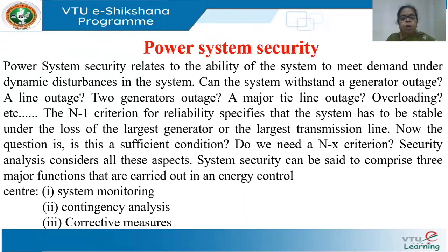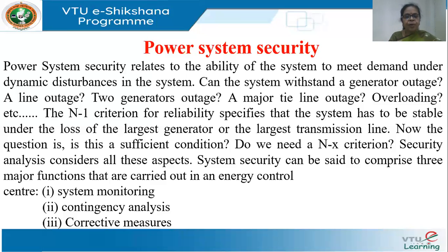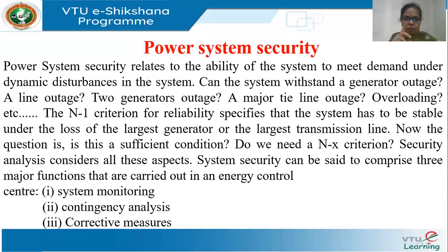Security considers all these issues. There are three major functions in security. The first one is system monitoring — obviously I have to monitor parameters and know when I am threatened. It is like having insurance but also periodically doing medical tests to know when your health is disturbed. So I keep monitoring system parameters to know when my system is in danger. You monitor the voltages, frequency, and power flows in the lines — so you will know when a line is overloaded. If frequency is coming down, it is an indication that my system is getting stressed.